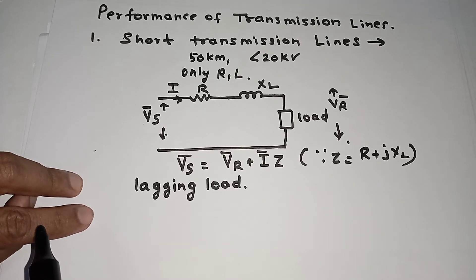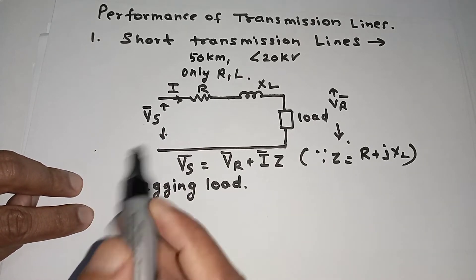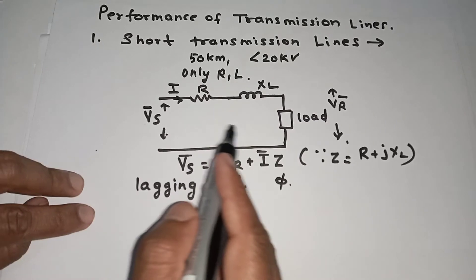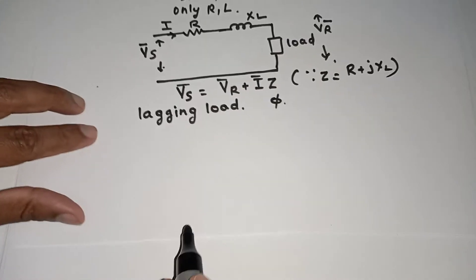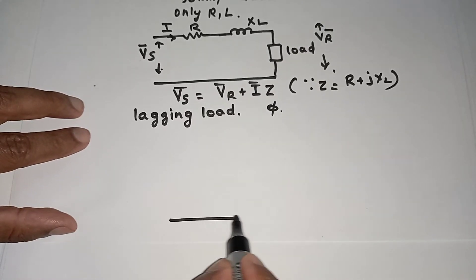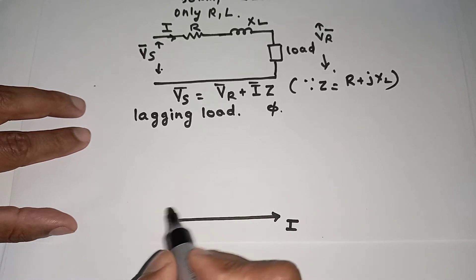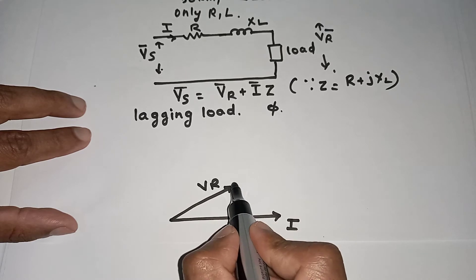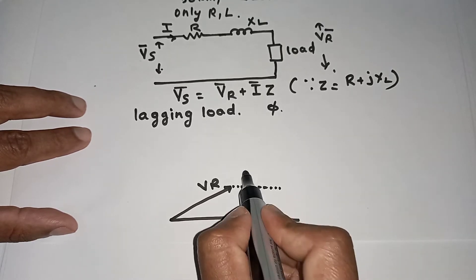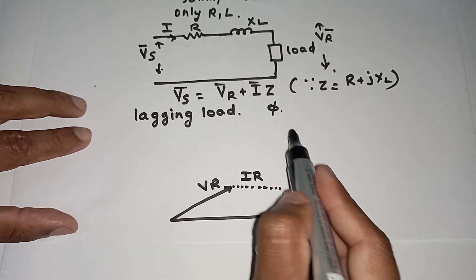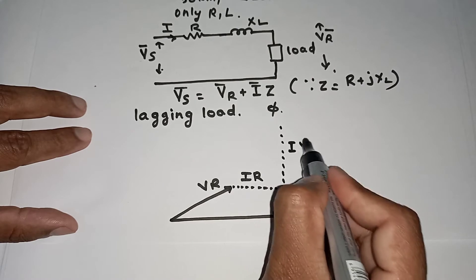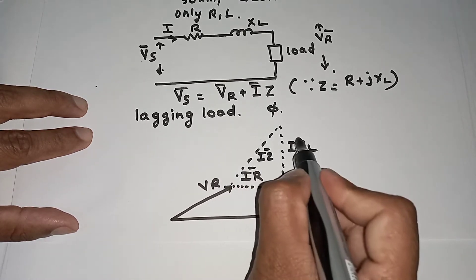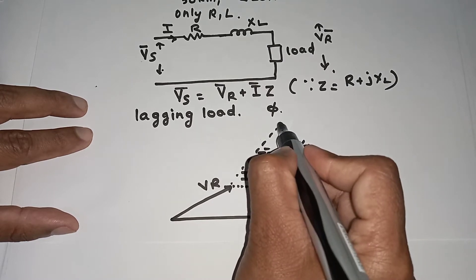For a lagging load, the current lags behind the voltage by some angle phi. Now we'll make the phasor diagram of this short transmission line. First, we draw the reference current phasor, then VR, the receiving-end voltage. Along the horizontal, the drop in the resistive part is I×R, and perpendicular to it is I×XL. The resultant is I×Z, which are all vector quantities.